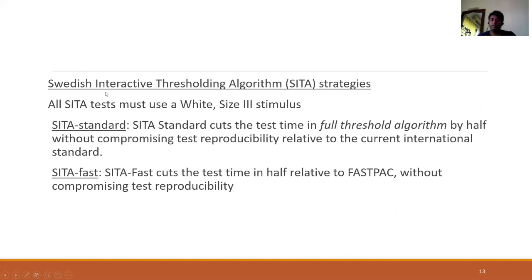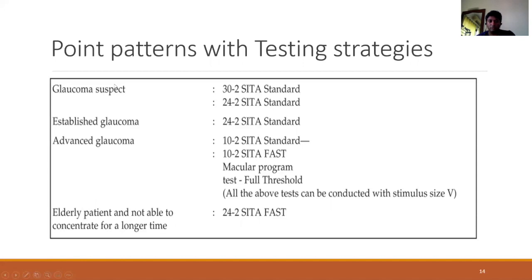The SITA strategies — Swedish Interactive Thresholding Algorithm — work based on the patient's responses. Once responses reach a statistically significant level, the perimeter stops presenting stimuli. This cuts down the total testing duration, increases reliability, and reduces patient fatigue without losing important data. SITA standard cuts the time of the full threshold algorithm by half, and SITA fast reduces the time of the FASTPAC strategy by half.